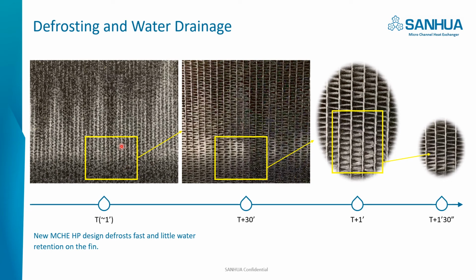The audience may want to know how well microchannel can drain the water during the defrosting process. We put several pictures of different defrosting times. The first picture is about 1 minute after the start of the defrosting. We can see that there is still white frost on most of the coil. And 30 minutes later, we can see that the frost is only at the bottom part, and on the other parts we see no clear frost.